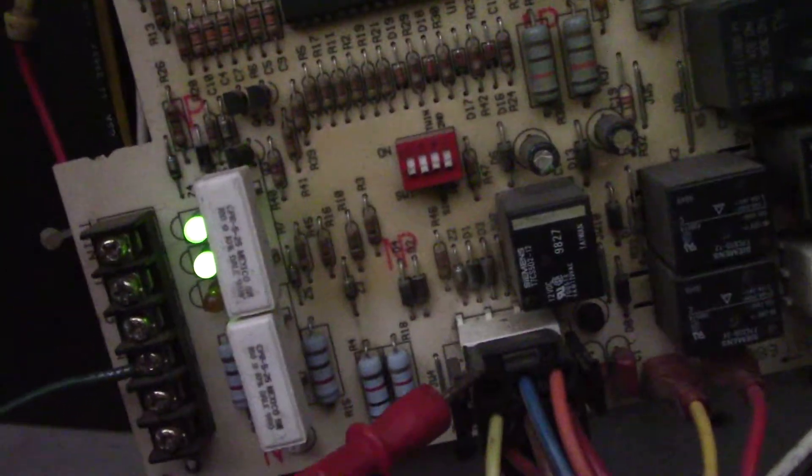As long as those lights are on, you know the board has 24 volts from the transformer here and you have the 120 volt power supply going through. If you take your meter and put one probe to R and one probe to C, you should read 24 to 27 volts if it's a more modern furnace.